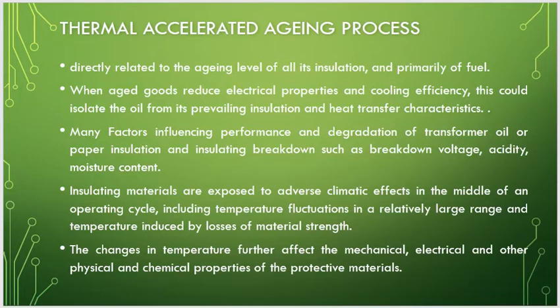Next, the thermal accelerated aging process. It is directly related to the aging level of the oil as insulation, and primarily of fuel. When aging occurs, the electrical properties and cooling efficiency are reduced. Many factors influence the performance and degradation of transformer oil or paper insulation and insulating breakdown, such as breakdown voltage, acidity, and moisture content. Insulating materials are exposed to adverse climatic effects in the middle of an operating cycle, including temperature fluctuation in a relatively large range and temperature-induced loss of material strength. The change in temperature further affects the mechanical, electrical, and other physical and chemical properties of the protective material.